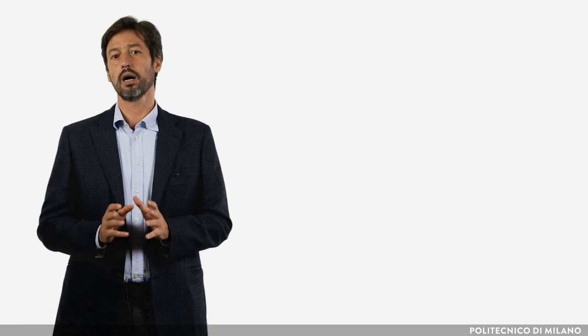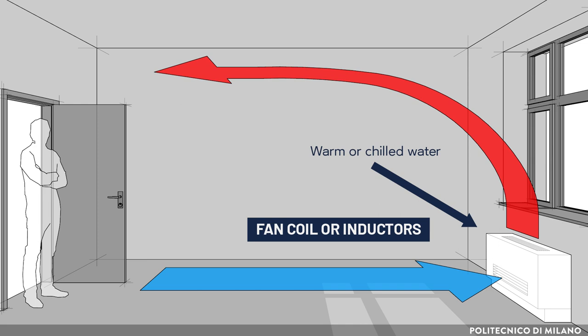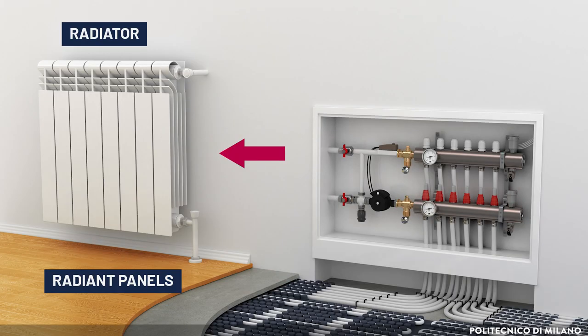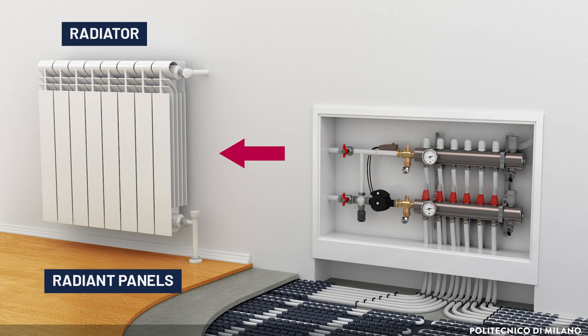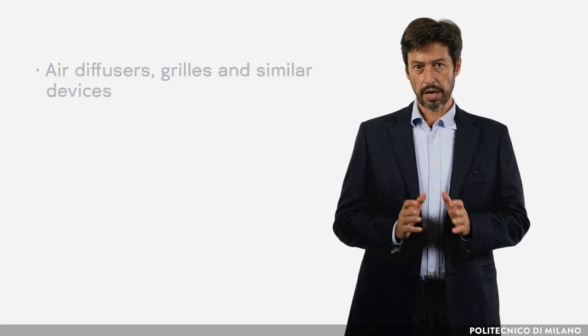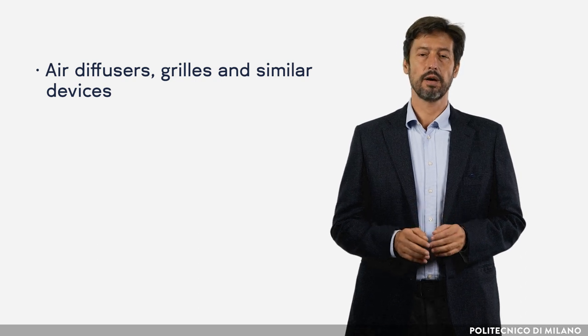The room terminals are devoted to deliver the heat carrier to the ambient to warm or cool it. When using water, they are usually fan coils or inductors for all-water or air-water systems, radiators for all-water systems, and radiant panels for all-water or air-water systems. For air distribution and extraction, we have air diffusers, grills, and similar devices, utilized in all-air or air-water systems.